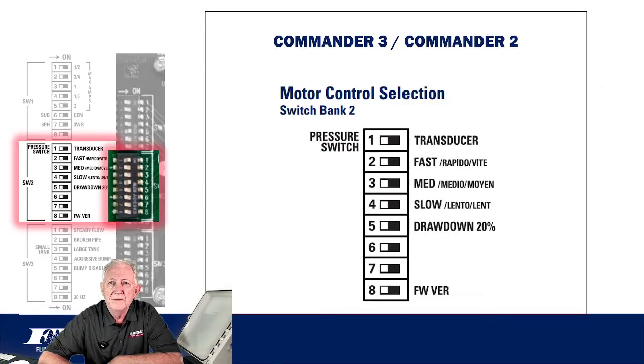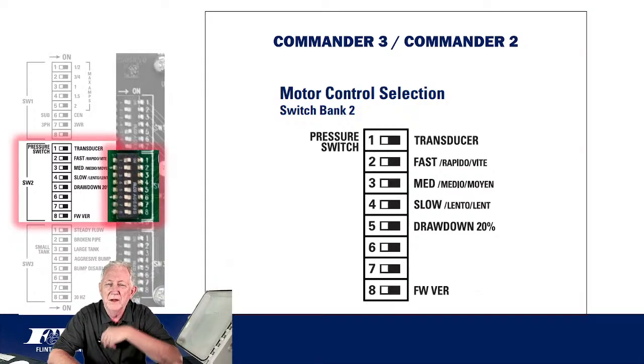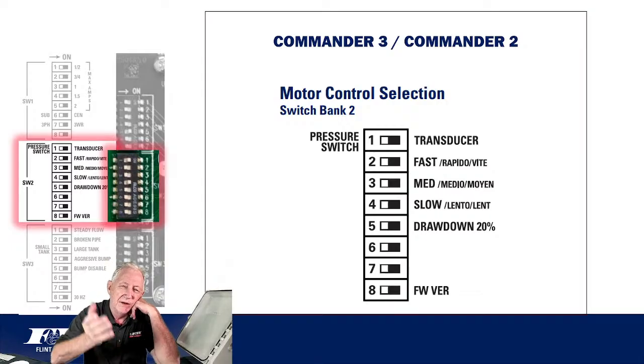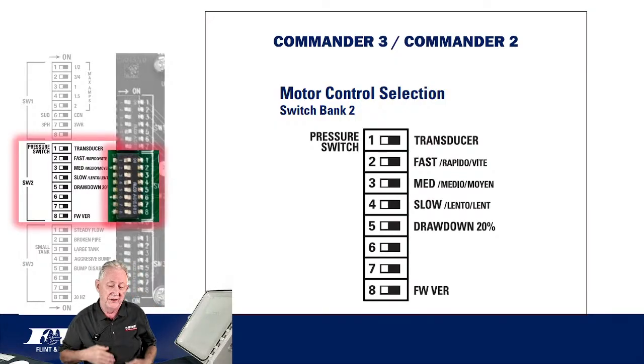Here's that bank in a close-up mode. But again, when you're setting this drive up, you're going to set it up for what motor you're running. Submersible based on horsepower, centrifugal based on max amps. Then you're going to come down to this bank and choose either a transducer or a pressure switch, right? Either one, because this drive will operate with either one.